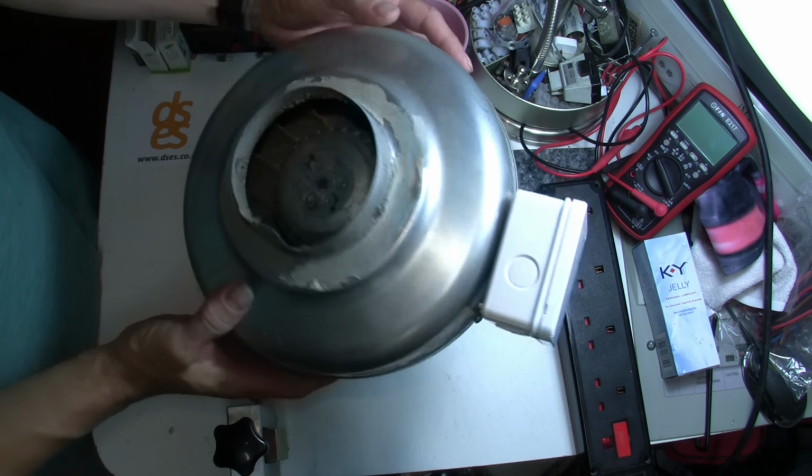Well, chill, because we can add in an external timer easily enough by placing it before the fan itself and feeding it on a permanent line so that it always has power. Now when a switch line hits the timer from either bathroom light switch being on, it will output to the fan and set it spinning.